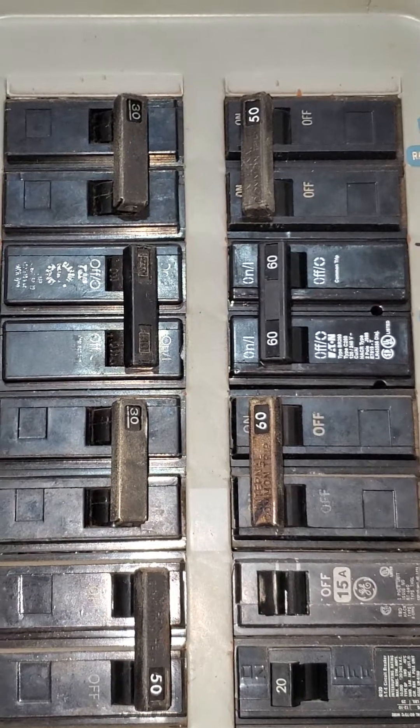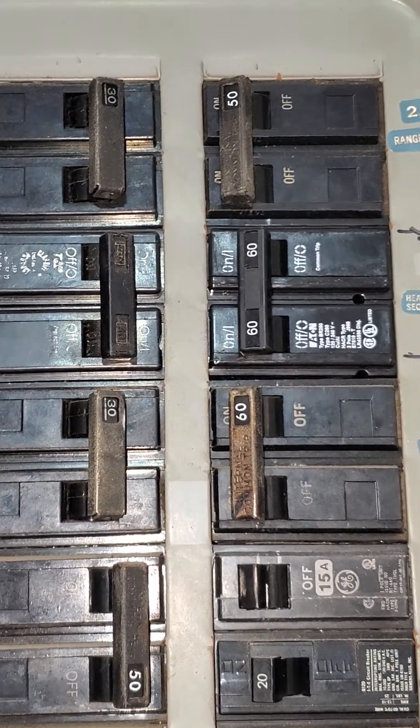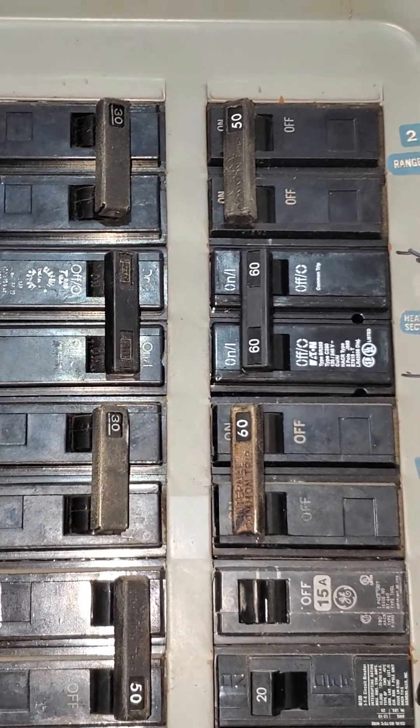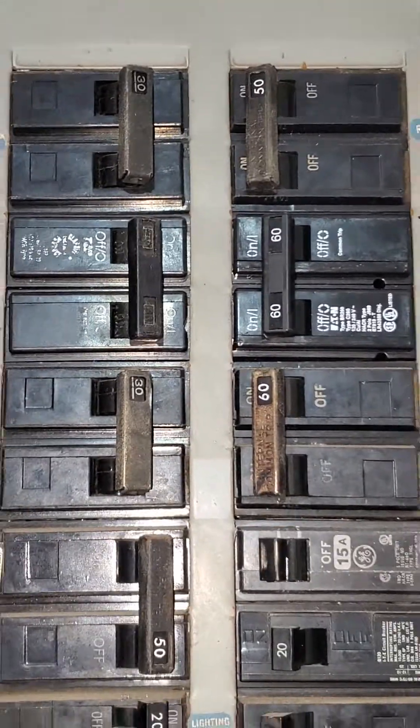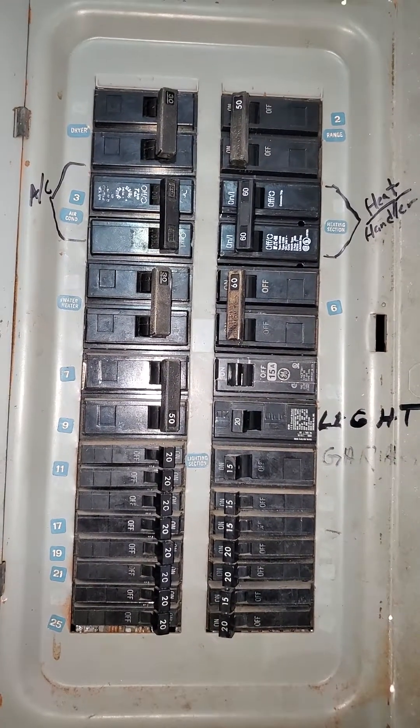Can we figure out the amperage here? Nope, we cannot. Don't add all these up to get the amperage — simply leave a blank or type in 'cannot determine.' Little tutorial on split bus panels.